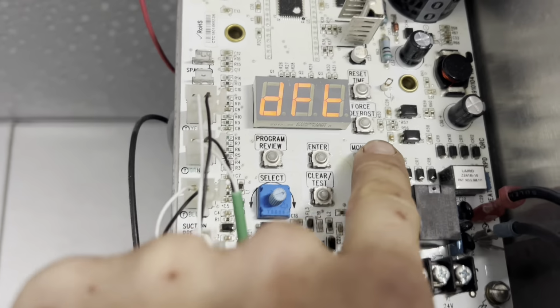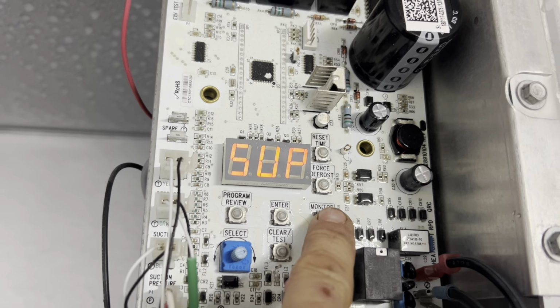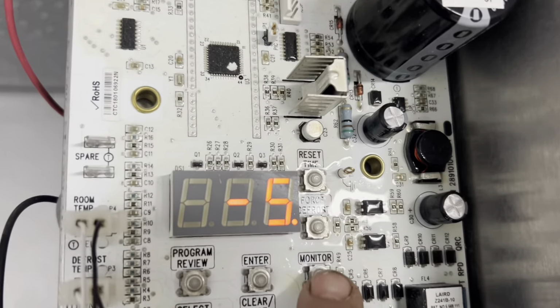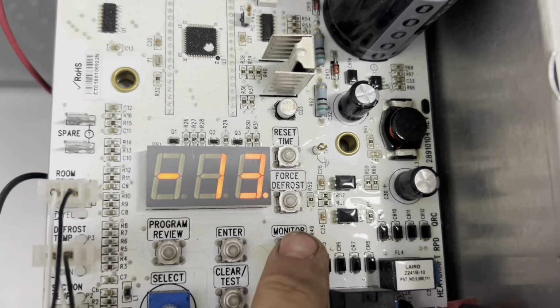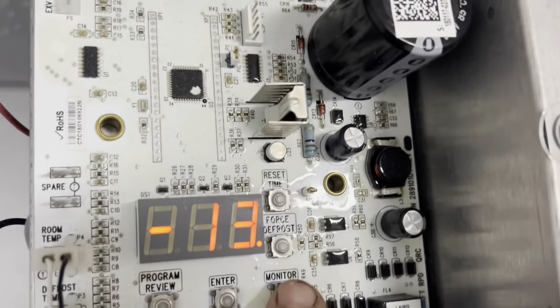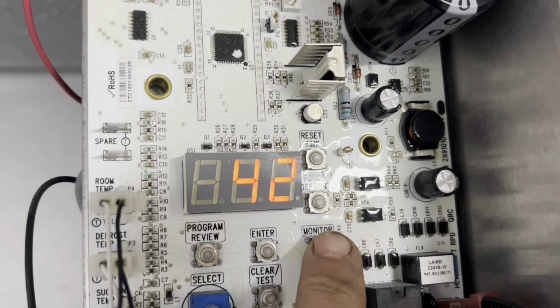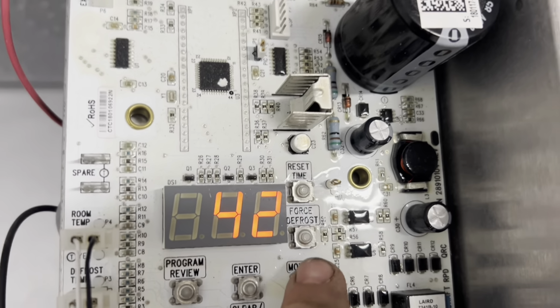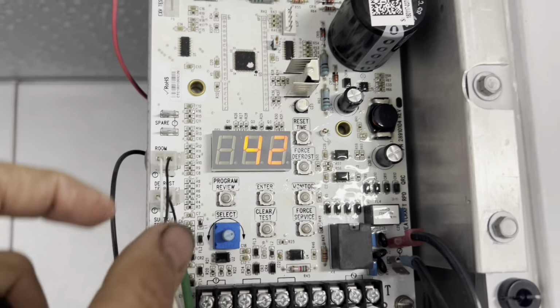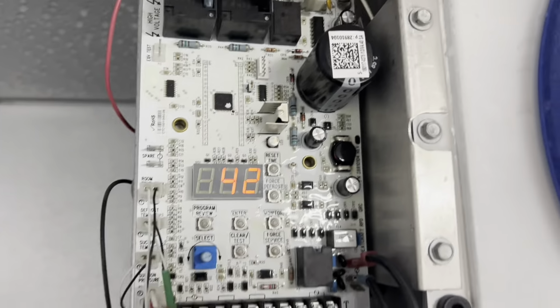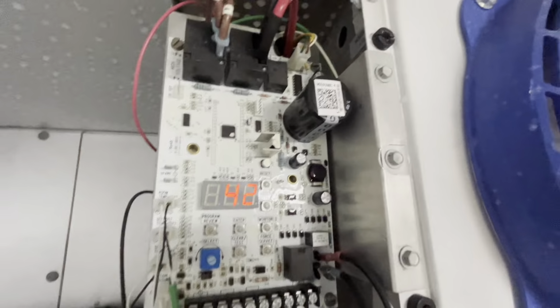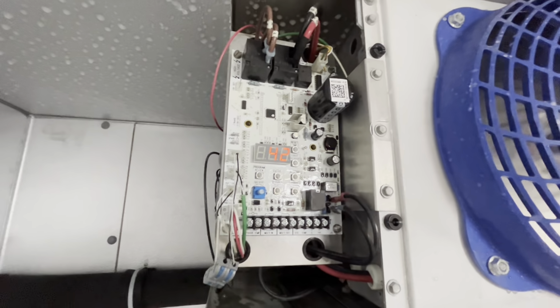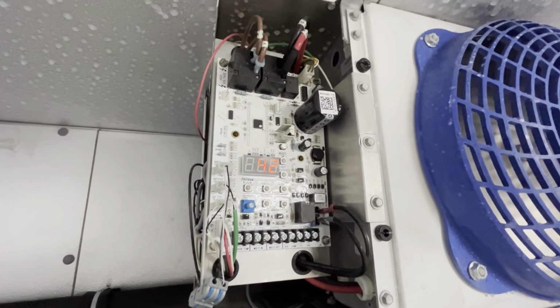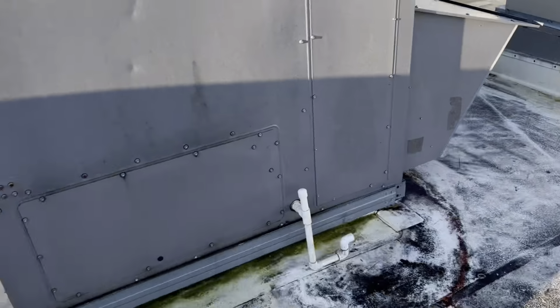Stand by. To the monitor screen. Let's go to suction. SST, I'm pretty sure that's the suction temperature at the coil. Yep. And then this is going to be my suction pressure. So yeah, 42 or 42. So that's correct. I just want to get some more temperature probes, and I think that'll solve the problem. The transducer's reading okay, and the temperature's reading okay. Again, you're -10 down here, you're -3 up on the roof, degrees that is.